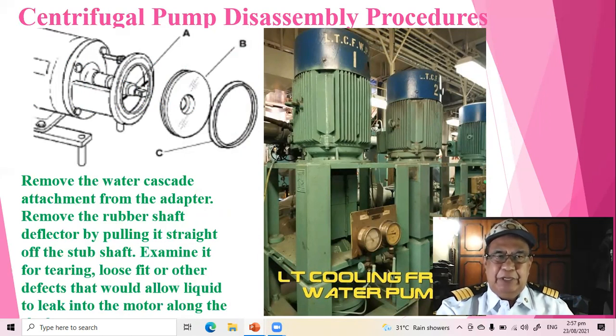Examine for tearing, loose fit, or other defects that would allow liquid to leak into the motor.